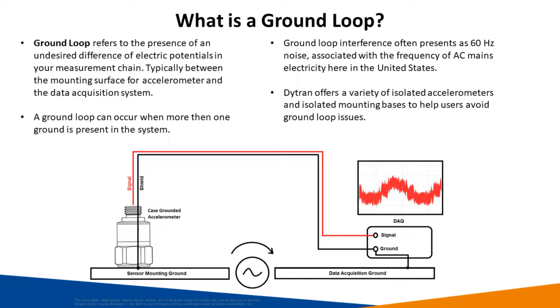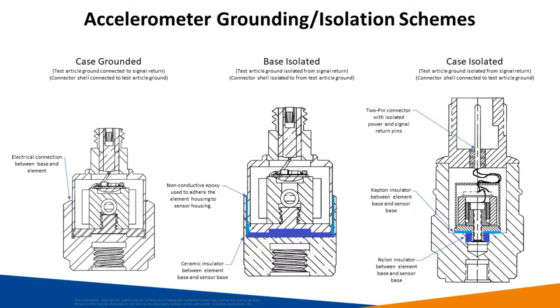Ground loop interference will often present itself as 60 Hz noise on your sensor data, associated with the frequency of AC mains power here in the United States. Dytran offers three types of grounding schemes, first being case grounded accelerometers. These are accelerometers that are grounded to the test article through the housing of the sensor. These sensors are typically smaller and more affordable than their associated isolated counterparts. The downside being that case grounded sensors can be affected by ground loop interference.